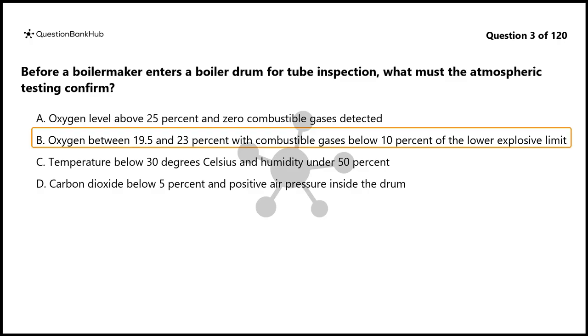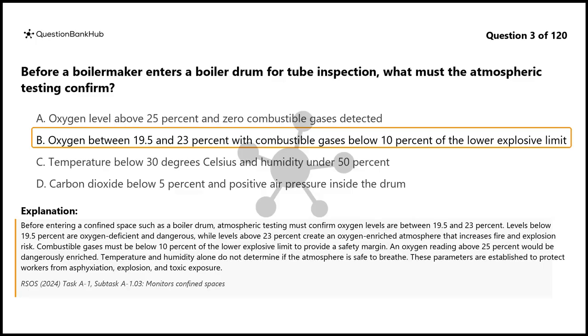The correct answer is B. Before entering a confined space such as a boiler drum, atmospheric testing must confirm oxygen levels are between 19.5 and 23%. Levels below 19.5% are oxygen deficient and dangerous, while levels above 23% create an oxygen-enriched atmosphere that increases fire and explosion risk. Combustible gases must be below 10% of the lower explosive limit to provide a safety margin. An oxygen reading above 25% would be dangerously enriched. Temperature and humidity alone do not determine if the atmosphere is safe to breathe. These parameters are established to protect workers from asphyxiation, explosion, and toxic exposure.